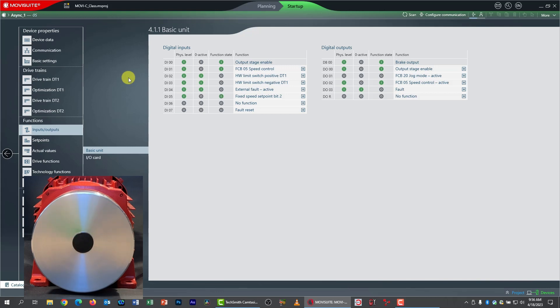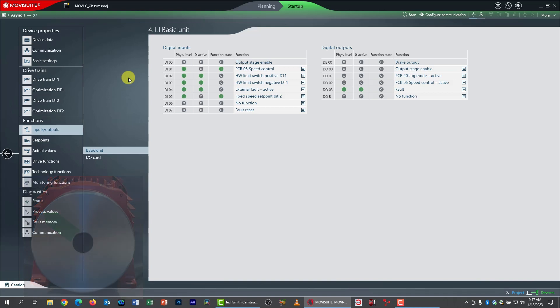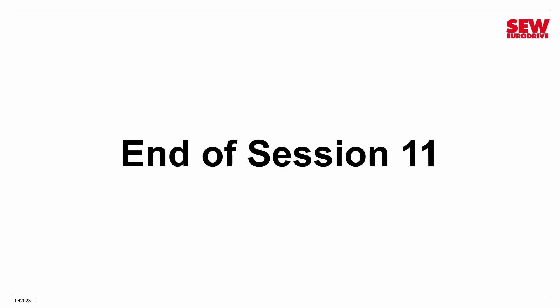Let me show one more stop type. I start the drive again and trigger a controller inhibit stop by turning DI00 off. It stops really quickly because my drive has a brake on it — it actually kind of jumped. There's no ramp, so there was no way of predicting how fast that would be. It was very fast here because it's an unloaded demo unit with a brake. In a real-world application with a big load, it could run for a while. You've now seen all four stop types discussed.